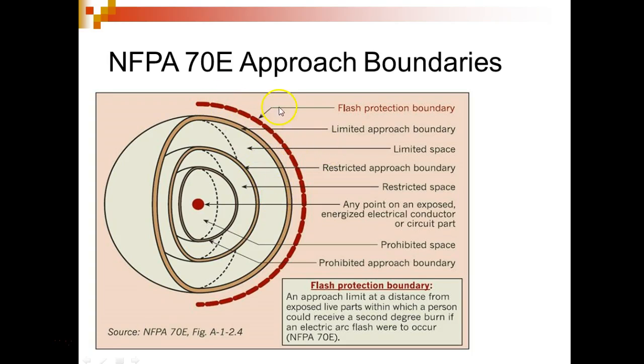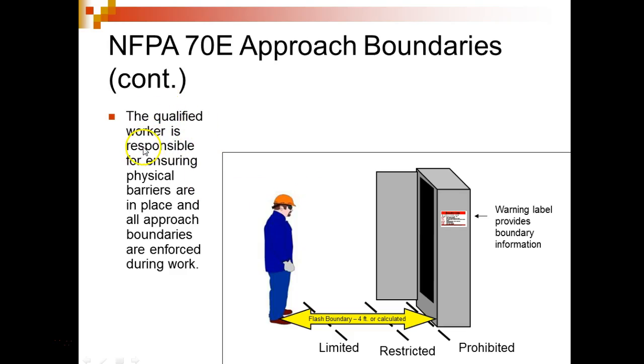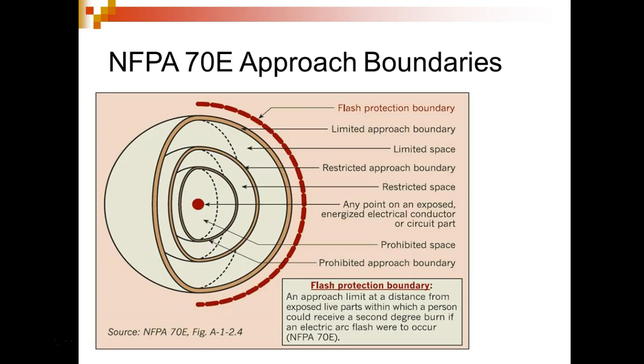We have different approach boundaries. We have a flash protection boundary, a limited approach, a limited space, a restricted approach, a restricted space, any point on the exposed energized electrical circuit, prohibited space, which nobody gets in, right? And then the prohibited approach boundary. They calculate all these. Qualified workers are responsible for ensuring physical barriers are in place and all approach boundaries are enforced during work. So if you go to work at a company that's got a pretty high arc flash rating, you're going to see boundaries on the floor. And they have to put those on the floor, which say, okay, within this boundary you can walk this safe distance. You're outside the arc flash, arc blast. Then you get into this distance, and you're going to have to start putting on personal protective equipment. And the closer you get, the more PPE you've got to wear, and the more training you're going to have to understand.